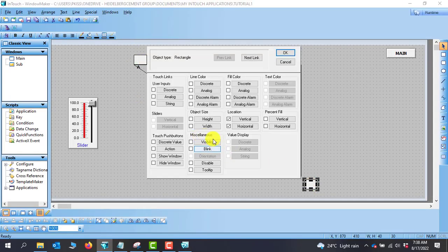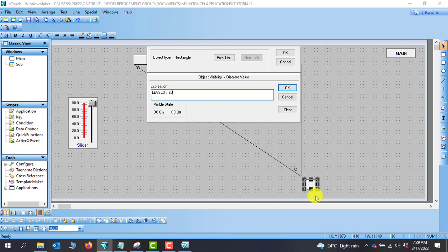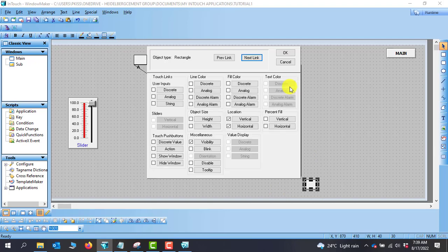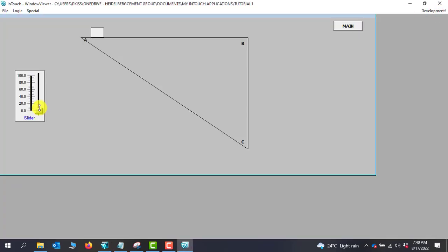We go back to the development page and assign a visibility property. Under the miscellaneous tab, we see Visibility. Double-clicking, we give it an expression: when Level 3 is greater than 60, this object will be visible. When it's less than 60, we shouldn't see it. We click OK — visibility is now ticked. Going to runtime, we can see that below 60 this object is not visible.